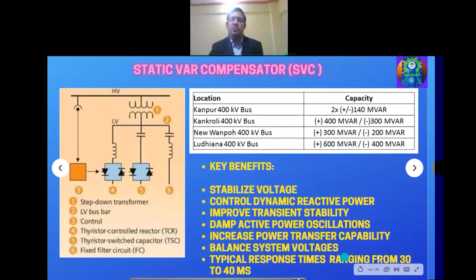The typical response time ranges from 30 to 40 milliseconds. So within this 30 to 40 milliseconds, it comes into function. Suppose there is a fault or some emergency situation or contingency in the power system. In that case, the response time of this static var compensator is 30 to 40 milliseconds, and within that it will try to stabilize the system against whatever fault is on it. So that is the typical response time of static var compensators.